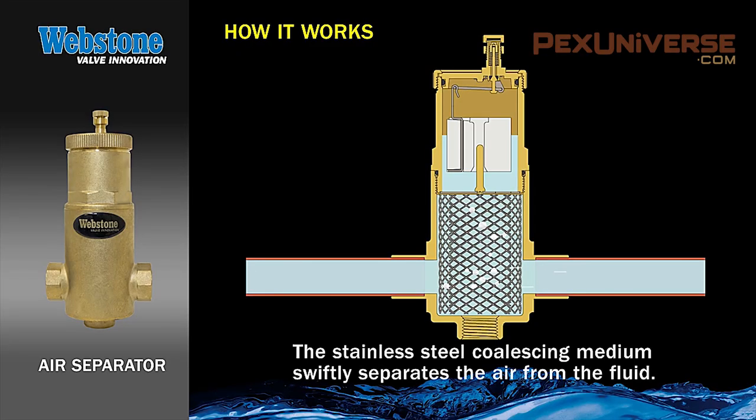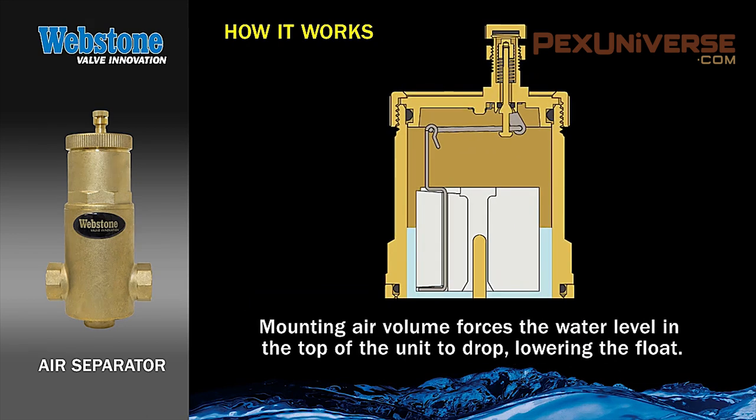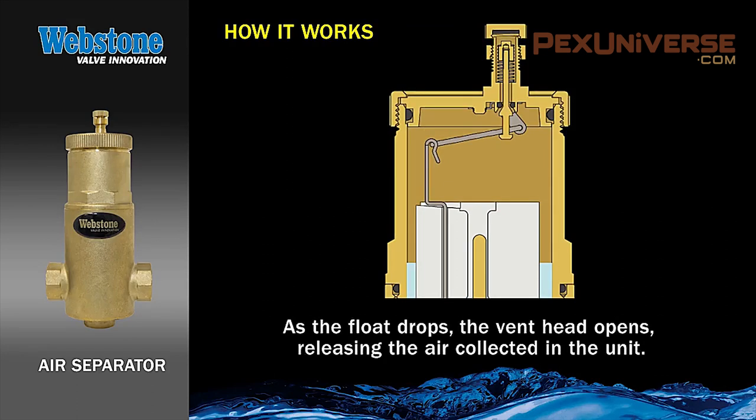This is an air separator. It has the same basic process as air eliminators but air separators may include a mesh mechanism that breaks down air bubbles before being released through the top vent as you can see here. Other than that it has the same float piece system inside.